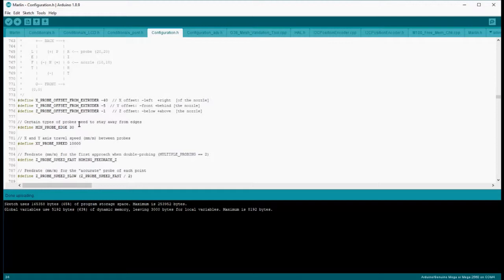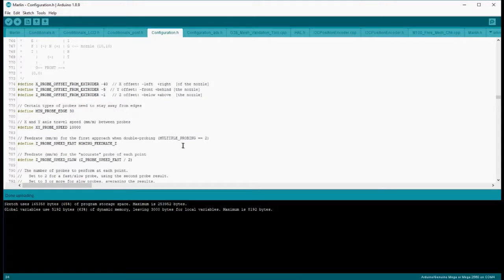I also changed this one from I think it was 10 up to 30, so it had a little bit more clearance. Because my probe is actually 30 mil further across than what the default is, I needed to move it in a little bit further so it didn't try and probe over the edge of the bed. Not a good idea to do that. Probing speed I increased from 8,000 to 10,000. This is just the speed at which it travels between the probe points.